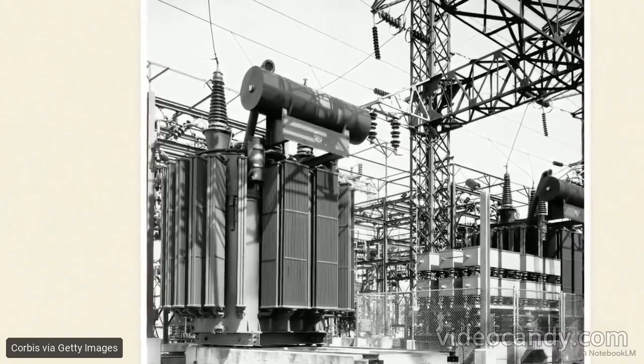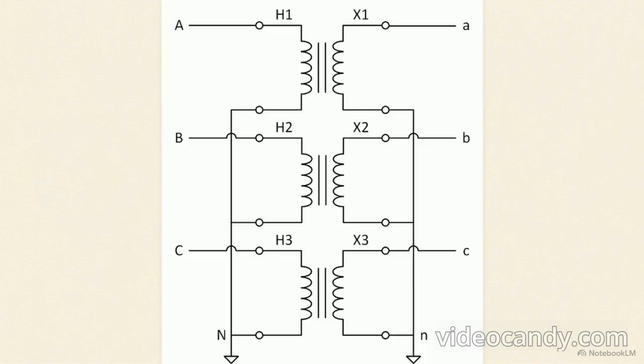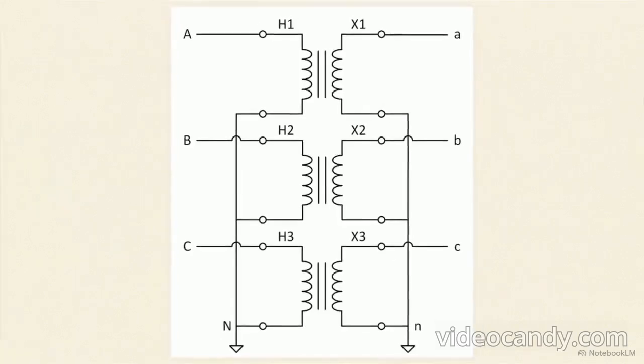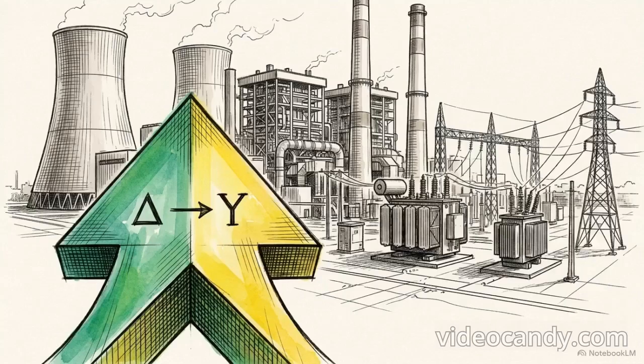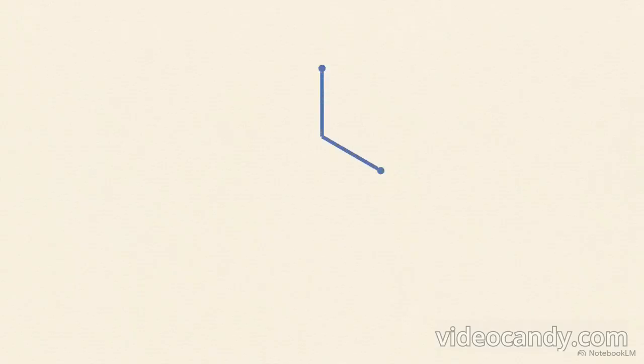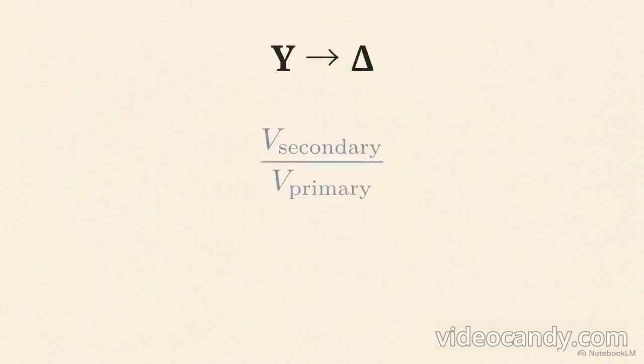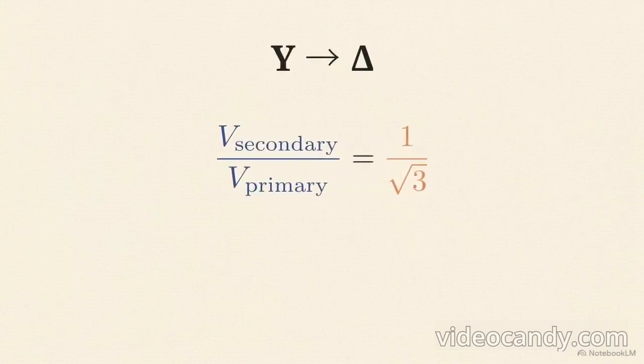Electricity rarely stays at a single voltage. Substations must constantly bridge high-voltage transmission lines with the lower-voltage distribution grids that power homes and businesses. This schematic details the internal windings of a YY transformer, establishing perfect baseline symmetry. To step voltages down at the end of a transmission line, engineers alter the symmetry, crossing the topologies to pair a primary Y connection with a secondary delta connection. Conversely, at generating stations, they use a delta Y setup to step the voltage up. This has the added benefit of providing a grounded neutral on the secondary side for distribution.